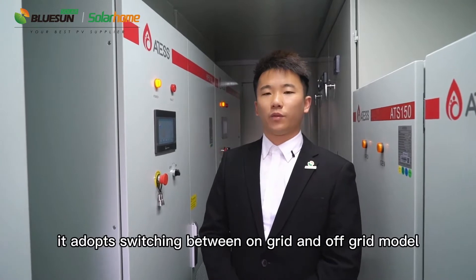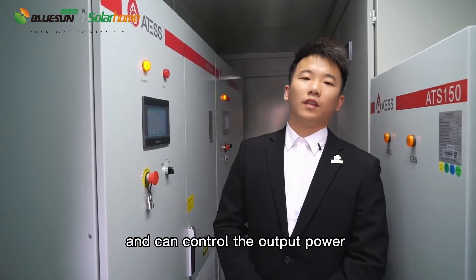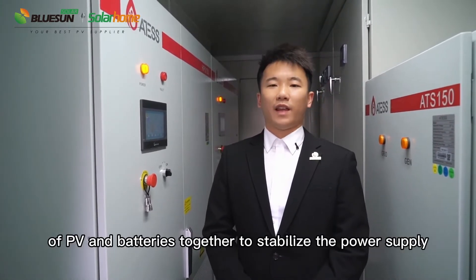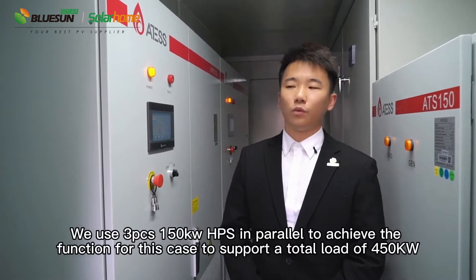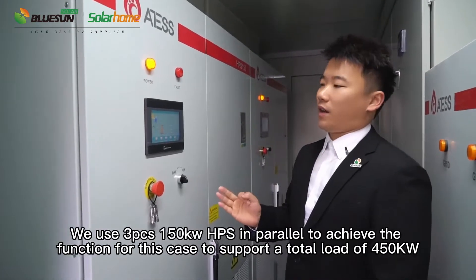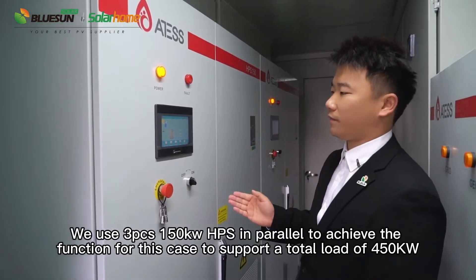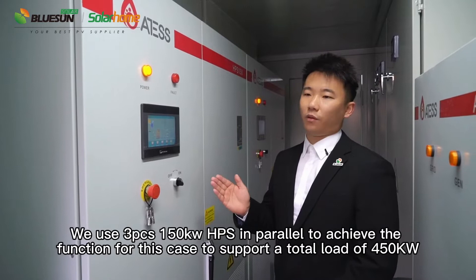It adopts switching between on-grid and off-grid modes and can control the output power of PV and batteries together to stabilize the power supply. We use three pieces of 150 kW HPS in parallel to achieve the function for this case, to support a total load of 450 kW.